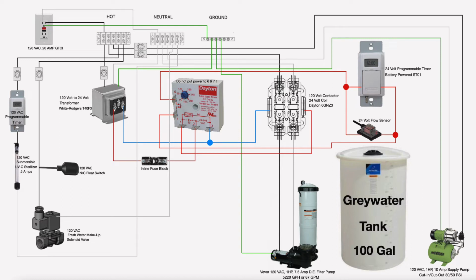Another thing you'll note, there is a freshwater makeup solenoid valve here. So that is for in the event that, say, you go away on vacation and you're not producing any gray water, you come home after a week or several days, you flush your toilet, but you don't have enough gray water in your gray water tank. That float switch will drop down inside the tank, close its internal switch, and send power to the solenoid valve. That'll allow fresh water to flow into your gray water tank and maintain a minimum water level so you don't cavitate or run your pumps dry, and so you always have water supply to flush and fill your toilets.